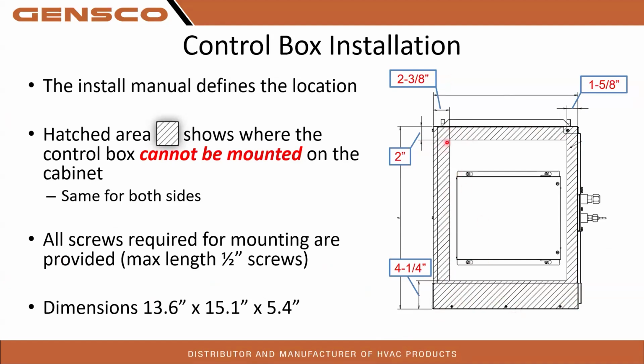So anywhere within this checkered gray box is where you want to screw mount the control box to your coil. It's the same for both sides. You do not want to use screws longer than 1/2-inch. Otherwise, you will end up piercing either drain pans or coils. So no 2-inch screws on that thing. 1/2-inch max.